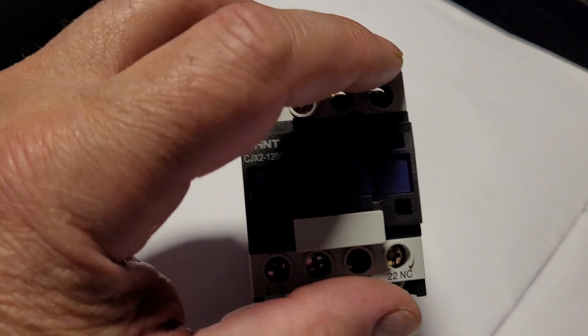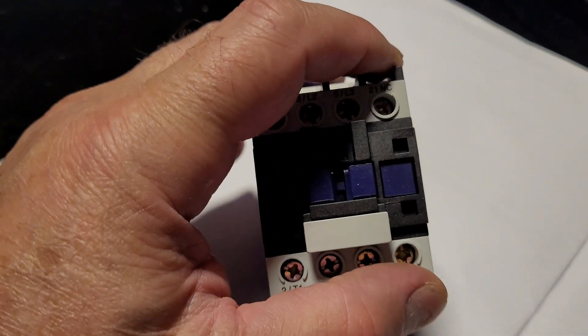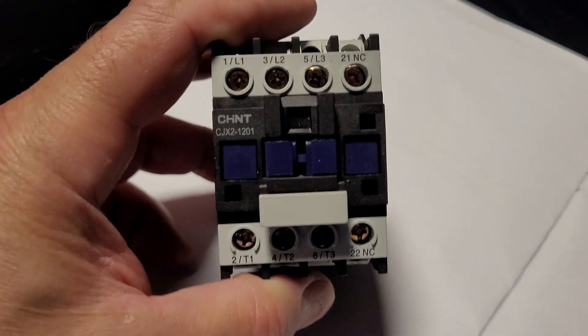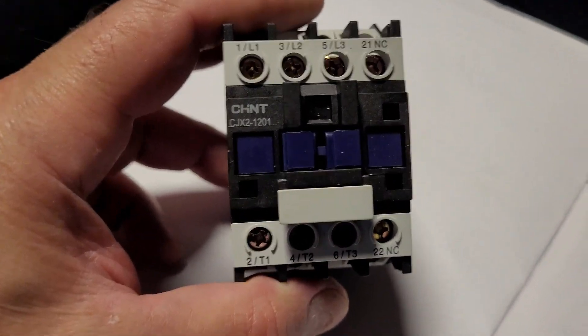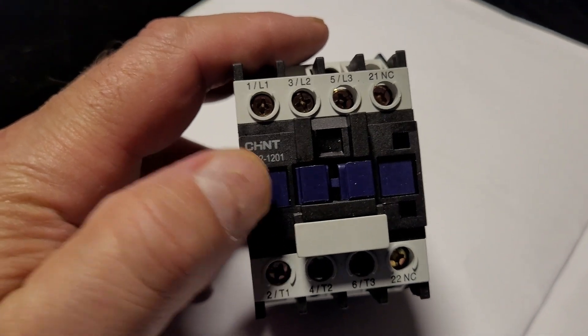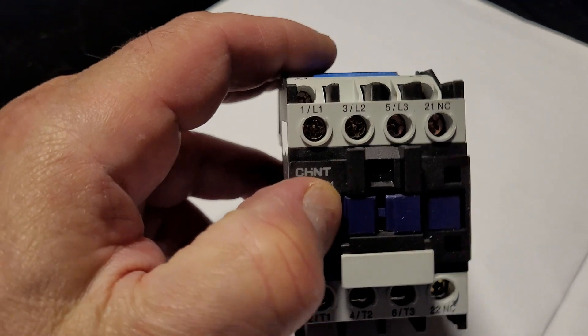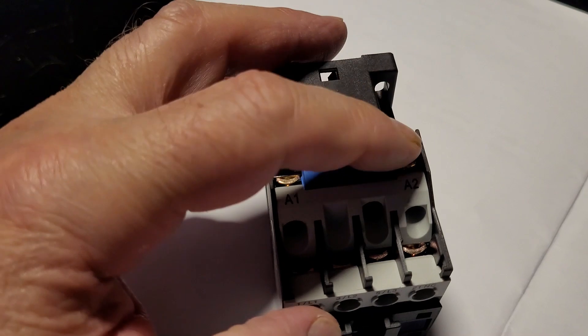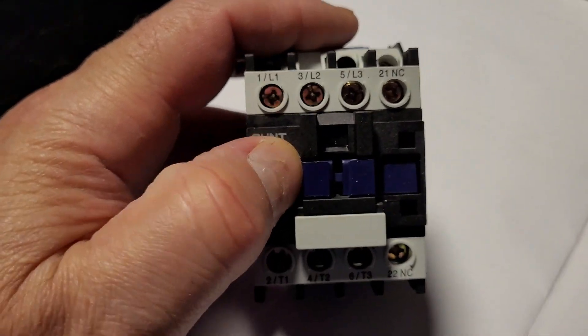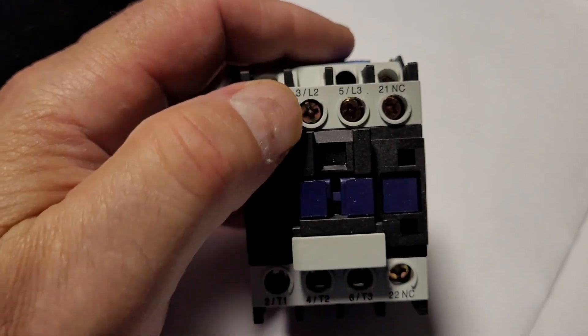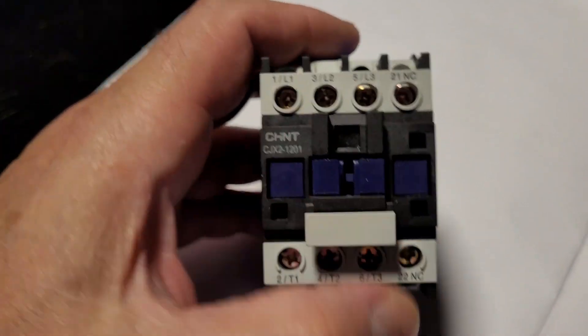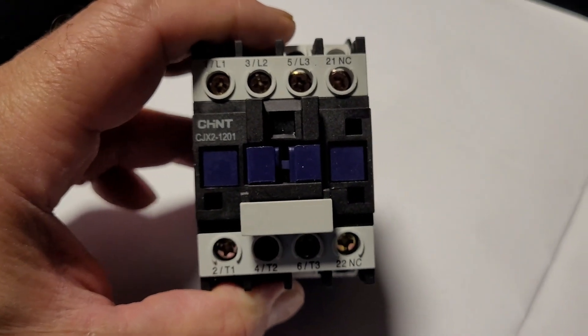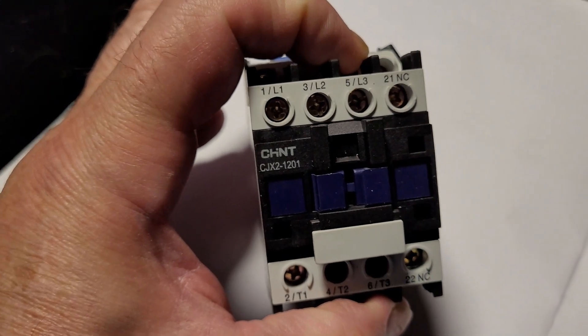I have two of these normally closed style and two of the normally open style, and those are the ones I've installed in the new circuit. Though it doesn't matter because I'm not actually making any connections across these anyway. But I'll have two extras, so if there's some problem over time, I can swap out the ones that are in there. So again, when this circuit energizes, when 24 volts is placed across A1 and A2, this pulls in and L1 connects to T1, L2 connects to T2, L3 connects to T3. In my case, I'm not using L3, so this third leg isn't being used.